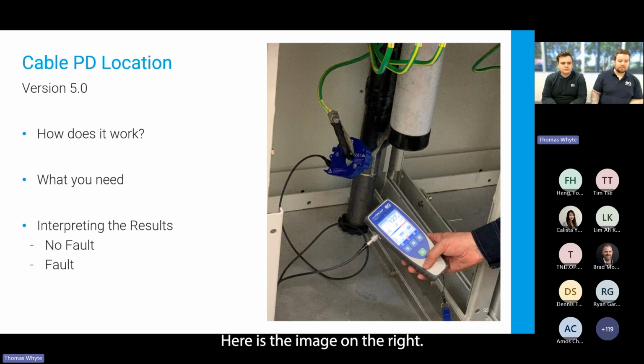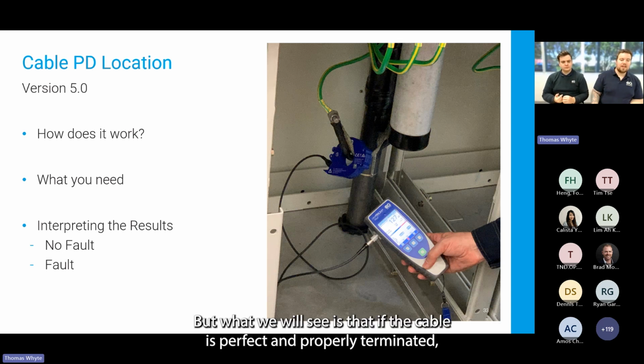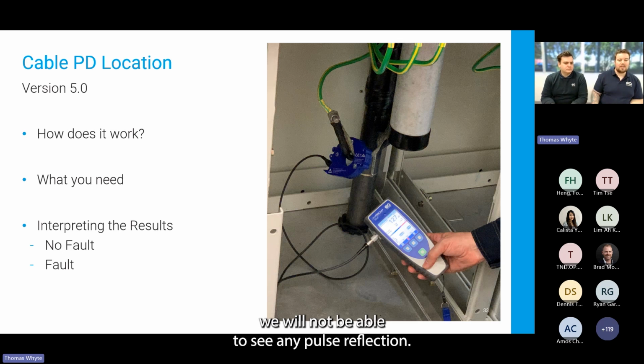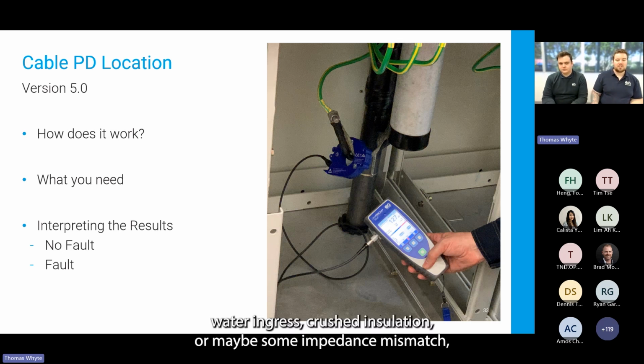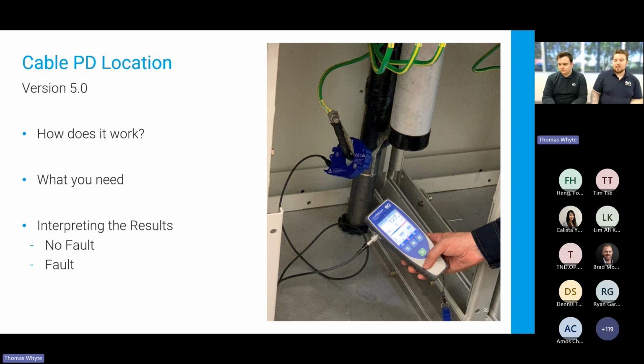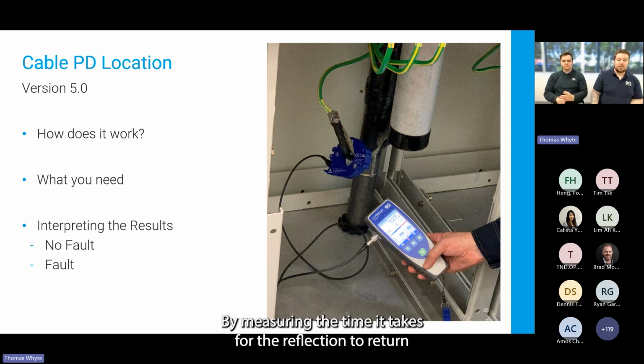Here is the image on the right. We can see that the UltraTEV Plus² has a HFCT attachment connected around a grounding strap of the HV cable. You can see that here. This type of test gets all the information required to find any PD locations along the cables. In the next slide, I'll provide an example of cable PD, but what we will see is that if the cable is perfect and properly terminated, we will not be able to see any pulse reflection. But if there is a fault, like a break, corrosion, water ingress, crushed insulation, or maybe some impedance mismatch, part of the signal reflects back to the source. By measuring the time it takes for the reflection to return and knowing the speed of signal travel in the cable, we can calculate the distance to the fault.